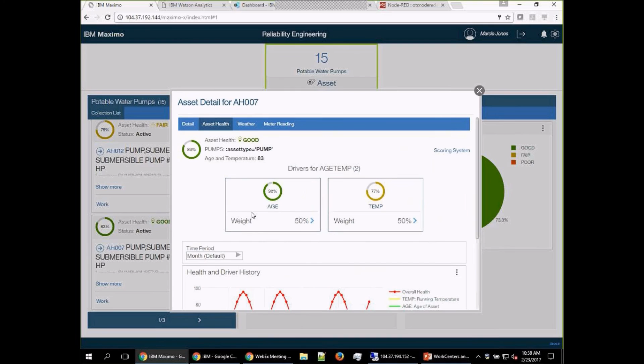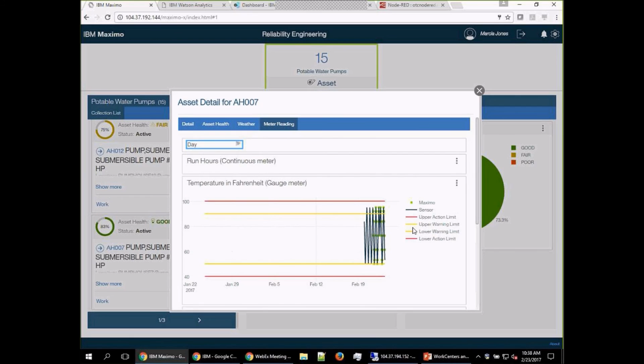Once I've accomplished that, it allows me to open up this trend, click on meter reading, and switch it back to a day view for more detail. You can see the blue lines coming in from the sensor, that's my Watson IoT data being pulled in on demand. As part of Maximo Asset Health Insights, you also get a new capability to read that periodically and store it as actual Maximo meter readings, which are the green dots here.